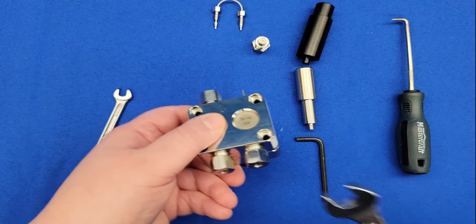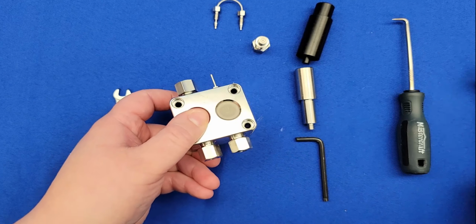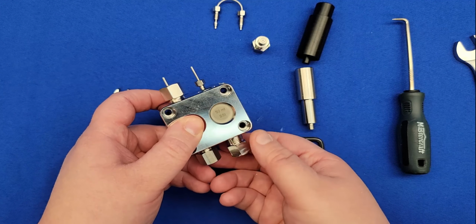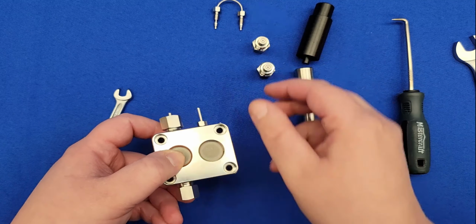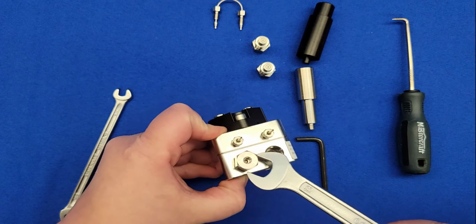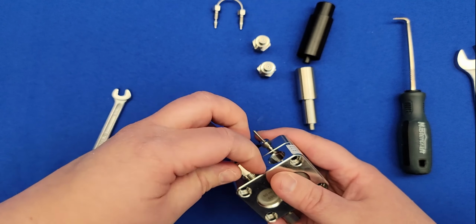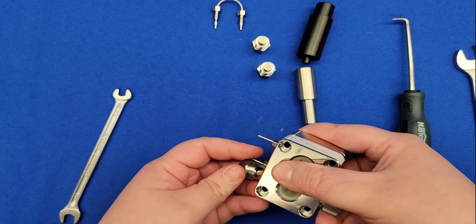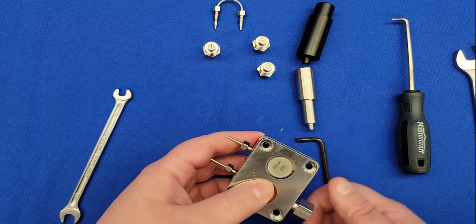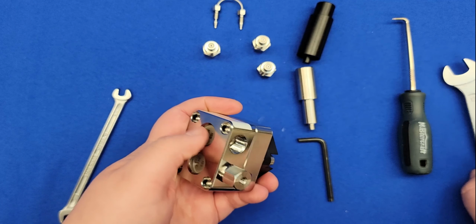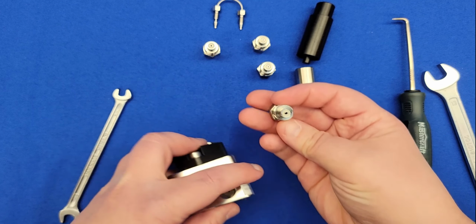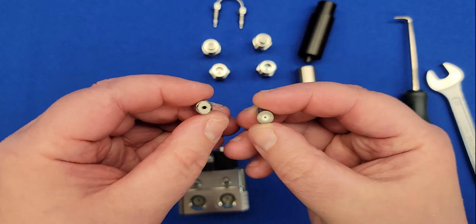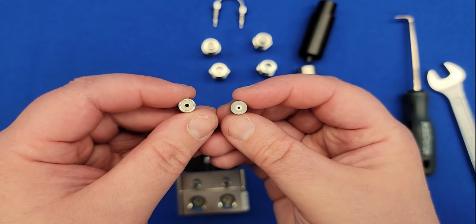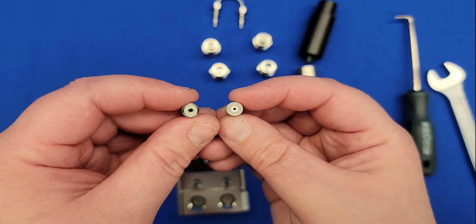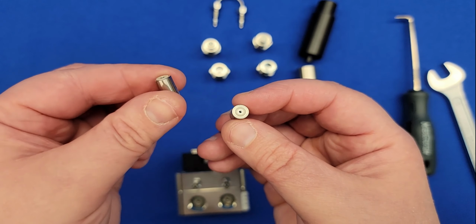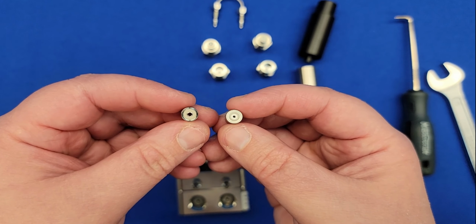Check valve, with the 13, then the dummy side, over here, the dummy side. As you can see, these are different. The dummy has a larger opening versus the check valve, because this is just a placeholder inside the pump head.